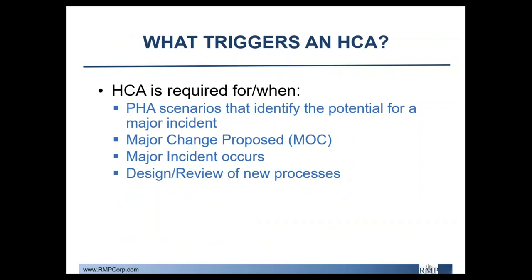An HCA is required to be performed for all PHA scenarios that identify the potential for a major incident — basically scenarios with a high health and safety risk rank such as loss of life, severe injury, or lost time injury. They're also required whenever you have a major change proposed at the facility, such as adding a new chemical, installing a non-spare vessel that increases inventory, or any change introducing the potential for more off-site impacts. An HCA is also required whenever a major incident occurs — any incident equal to or worse than a lost time injury — and during the design and review of new processes.